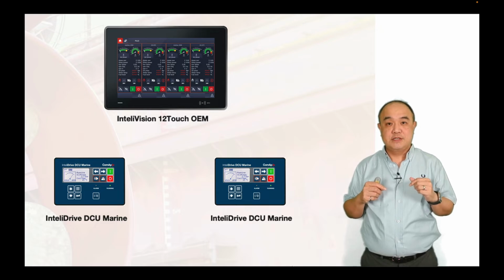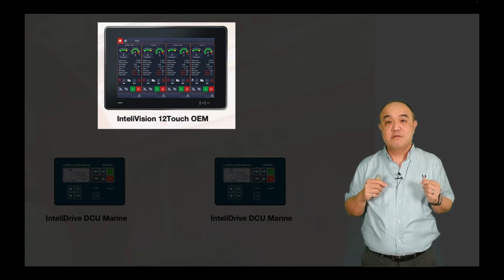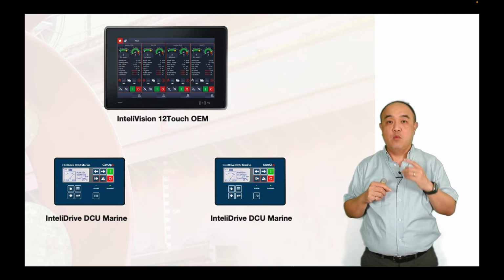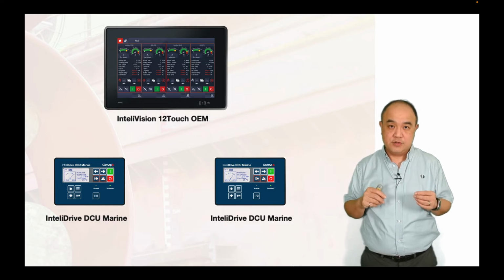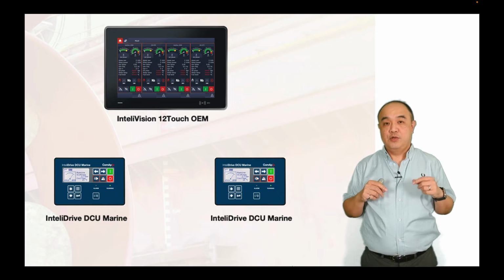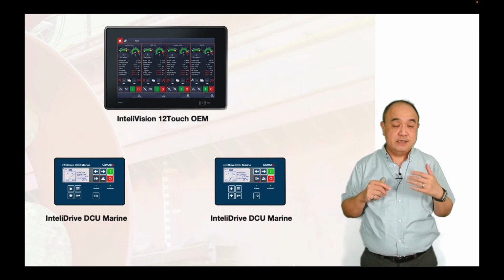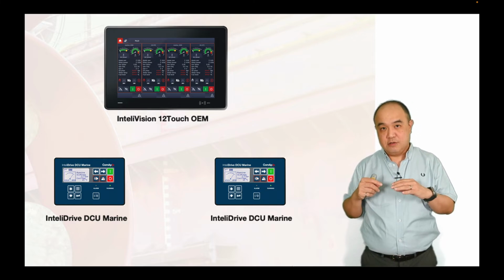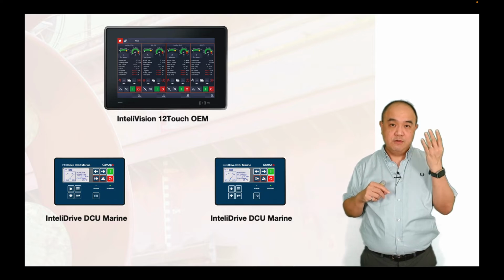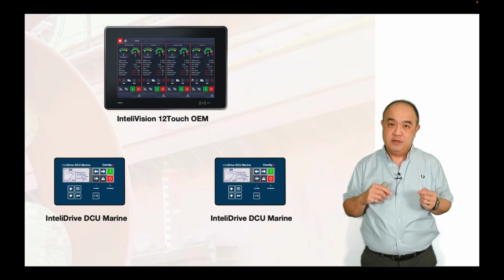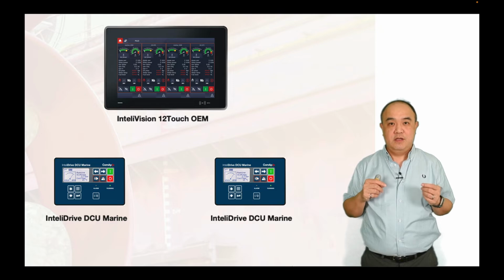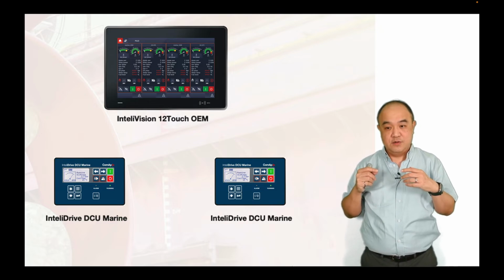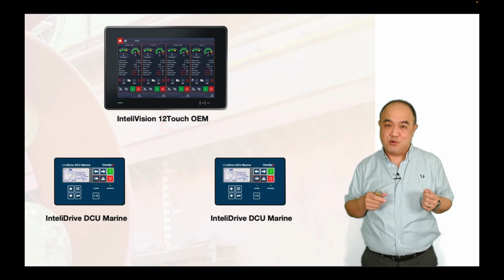The new product this year is the InteliVision 12Touch OEM. This big 12-inch display is similar to the one in the gas line, but this one is an OEM version with marine classification, and it can support up to 4 controllers on one display. So you can have 4 DCU Marine controllers using one display. You can also use this IV12T OEM to support, say, InteliGen NT BB, InteliSys NT BB, InteliGen NT base box, or GSC controllers—again up to 4 controllers with one IV12T OEM. This is a new firmware branch we have for the 12-inch touch display, so for those who want to use our 12-inch touch display for multiple gensets, this is the product for you. Let's take a look at the next slide.